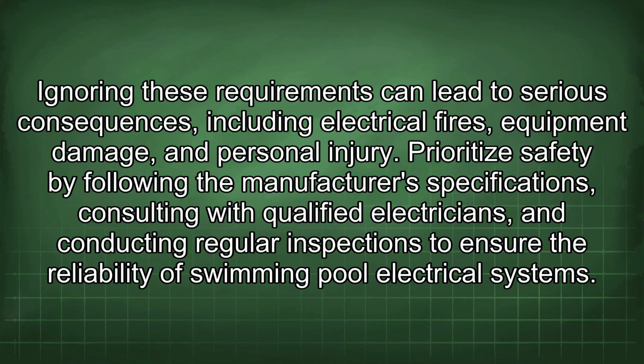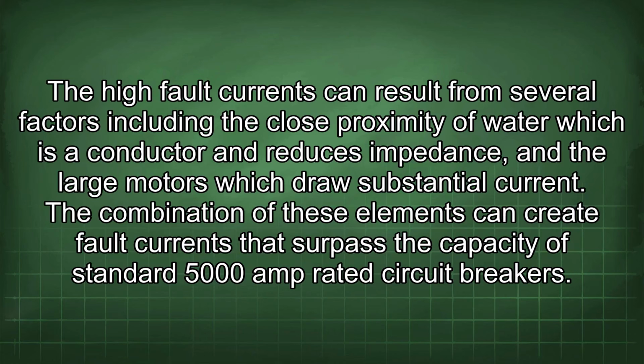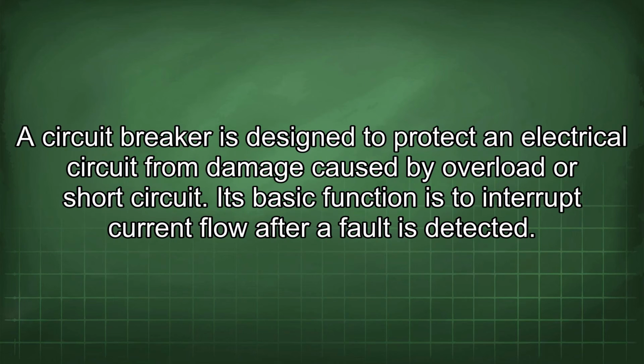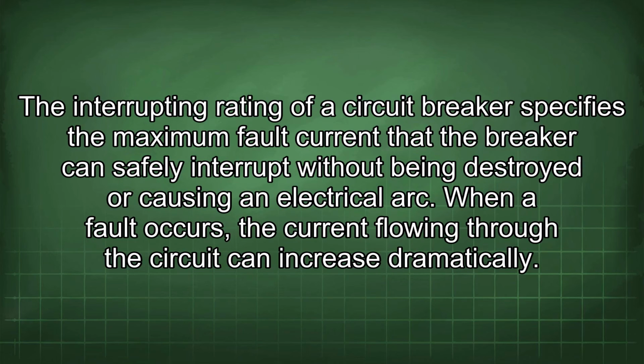The high fault currents can result from several factors, including the close proximity of water, which is a conductor and reduces impedance, and the large motors which draw substantial current. The combination of these elements can create fault currents that surpass the capacity of standard 5,000 amp rated circuit breakers. A circuit breaker is designed to protect an electrical circuit from damage caused by overload or short circuit. Its basic function is to interrupt current flow after a fault is detected. The interrupting rating of a circuit breaker specifies the maximum fault current that the breaker can safely interrupt without being destroyed or causing an electrical arc.